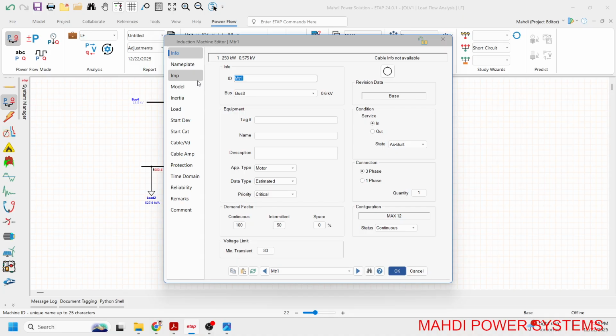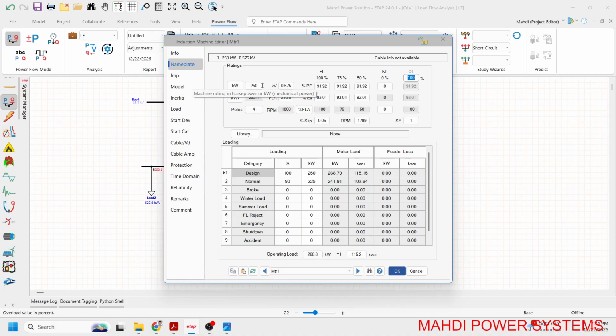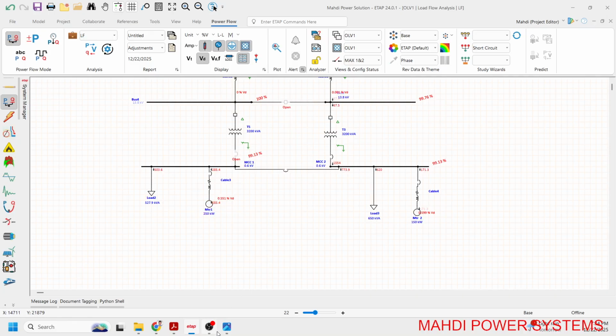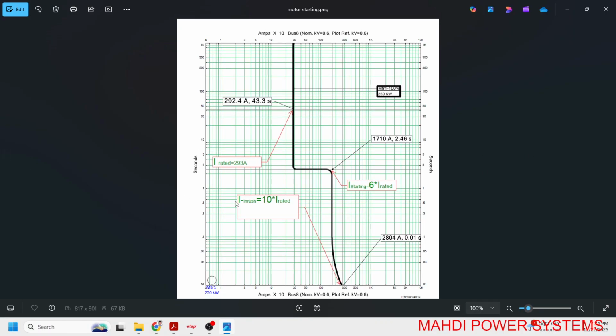This is the nameplate of the motors. 250 kilowatt and 293 amp. Here is the FLA, but this is the rated current, the current that is written on the nameplate. I prepared a sketch here. This sketch shows motor starting versus time. Here we have time, seconds, and here we have current.